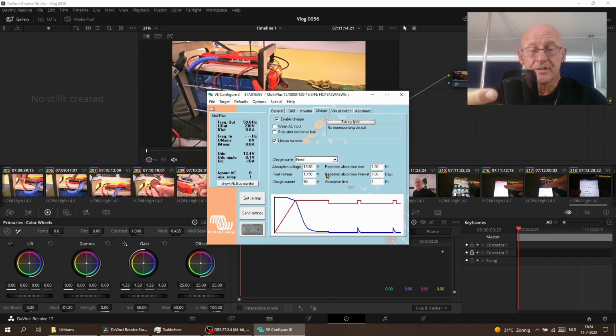I already changed this weeks ago, so I'm just showing you what I did. Charge curve is set to fixed, I don't remember why, maybe adaptive was an option too. Anyway, I changed the absorption voltage to 13.8 and the float voltage after the absorption phase to 13.5. That's high enough to fill it to about 90-95%, which is nice since lithium batteries have so much amp-hour capacity that you don't need to fully charge them.